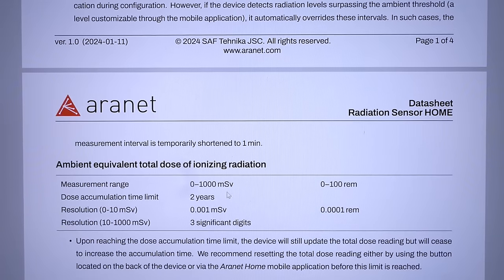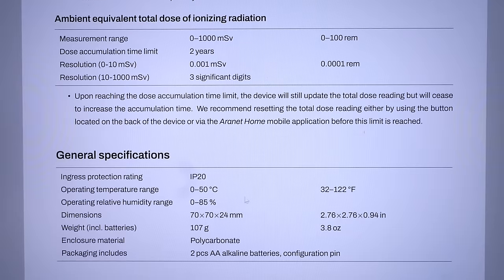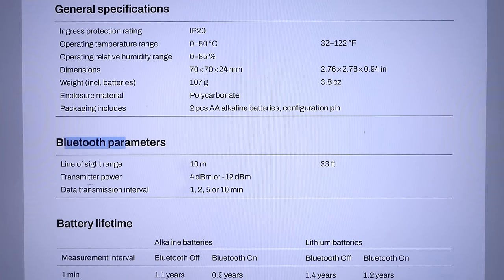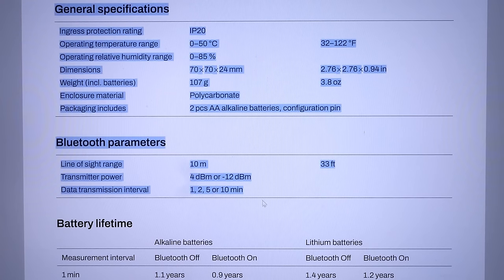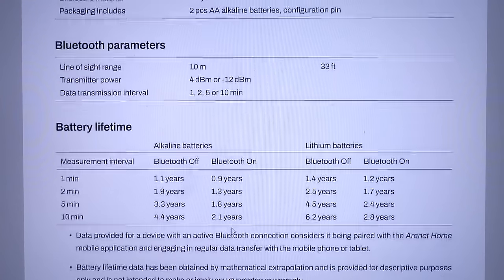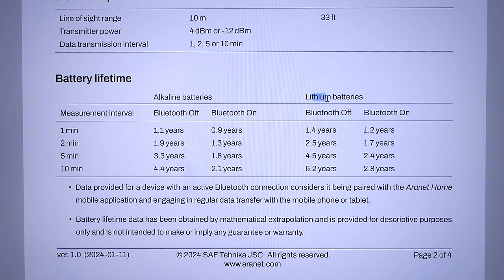And the ranges for the total dose, and some other specifications: temperatures, humidity, dimensions, weight, batteries, the Bluetooth. The data transmission interval is probably the same as the measurement interval, and the battery life for alkaline or lithium batteries with the Bluetooth off or on, at various measurement intervals.